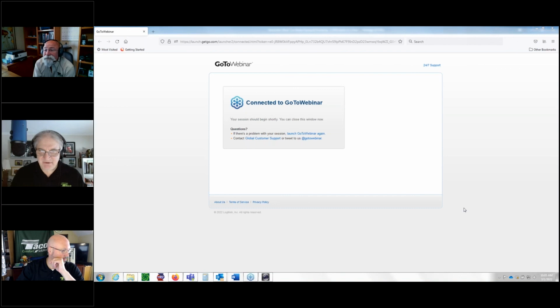This one just came in from William Sherwin. It appears that using a variable speed primary pump that allows for setting up the flow by Delta T versus old-fashioned flow measurement, the cost and time is much less, and the increase in accuracy is worth the extra initial cost of the pump. Yes, that's a statement we've been making for, oh boy, I'd say almost 10 years now. Delta T pumping is by far and away the most accurate and best way to run any hydronic system.